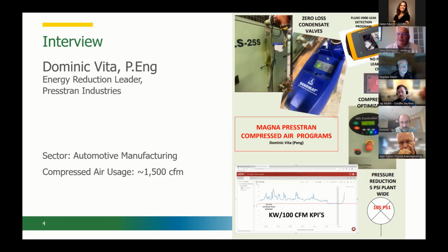Absolutely. Just a quick comment on that, Dominic, there aren't two plants that are identical, regardless of their stamping. And the amount of plants I've been in, no two plants are cut and paste where you can take a controller optimization that worked in one and believe it's going to work in the other one. Everyone needs to be analyzed individually to see what works. In this particular case, you've got three large horsepower units, virtually all identical in horsepower. Where's the energy savings other than on a fixed speed, eliminating the load, unload? That's why it's critical to look at how they're presently being operated and what you're doing on the weekend.